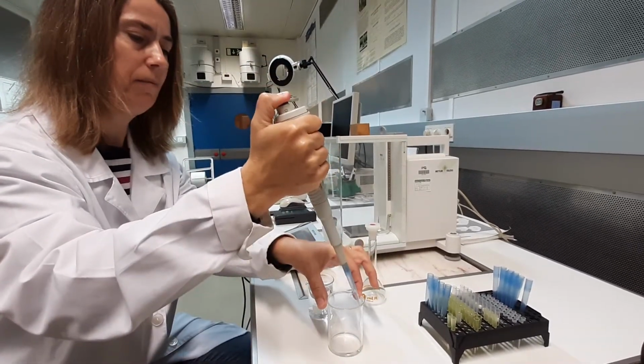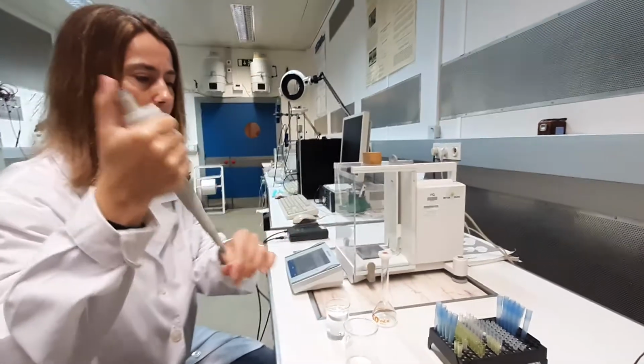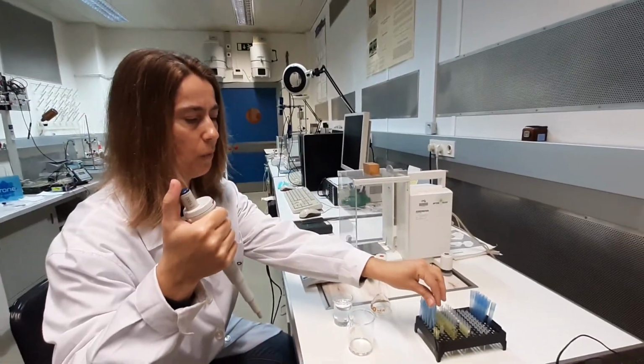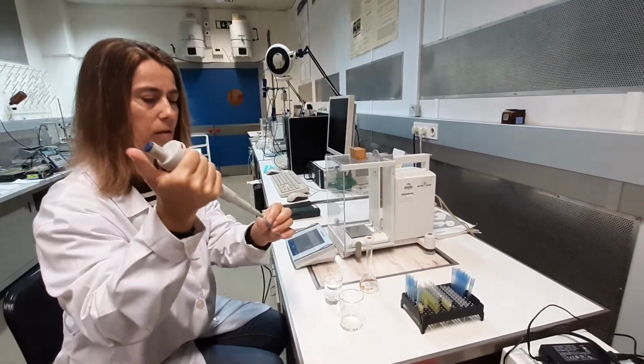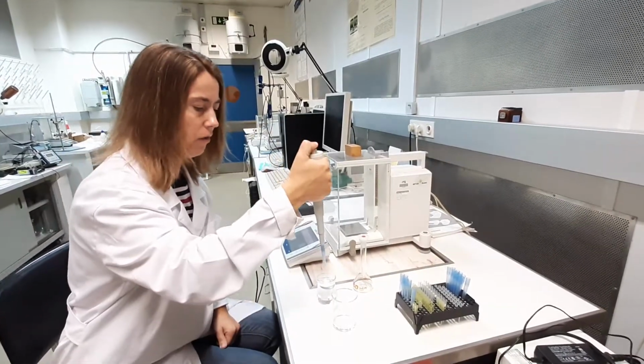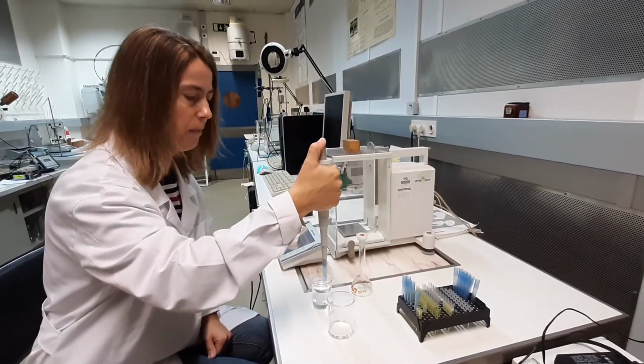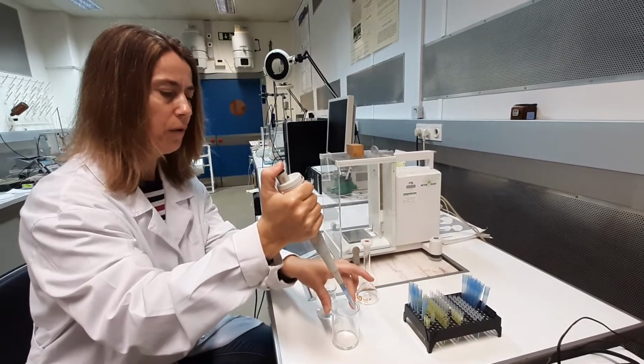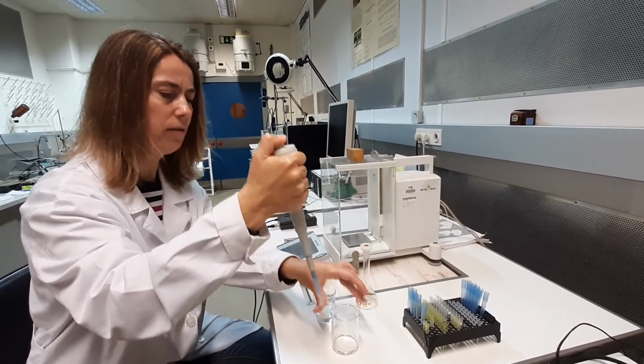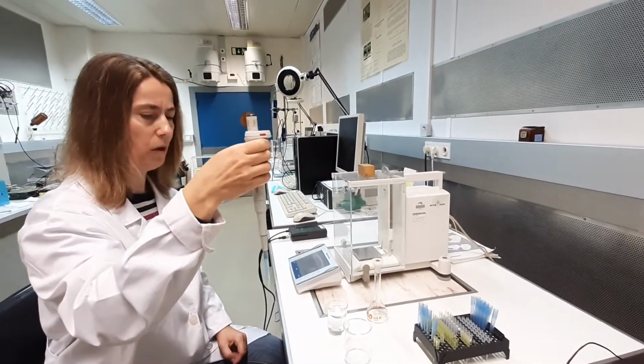Last time. And here we switch the tip. So we put a new tip on the pipette, we fill it again in order to also wet the tip. We discard this water, and at this moment the pipette is ready to start the calibration.